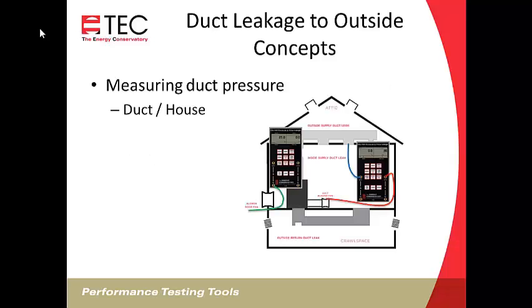When we're measuring the duct to house pressure, this is the setup. We're showing the setup for the duct to house pressure. So our blower door reference, we're measuring house with reference to outside on our blower door gauge, and we're measuring the duct with reference to house on channel A of our duct leakage gauge. So remember, like we mentioned before, we've got duct on the top, house on the bottom, duct to house pressure. We're in the house with the gauge, so we don't need to put a tube on there. You can put a tube on there if that makes you feel better.